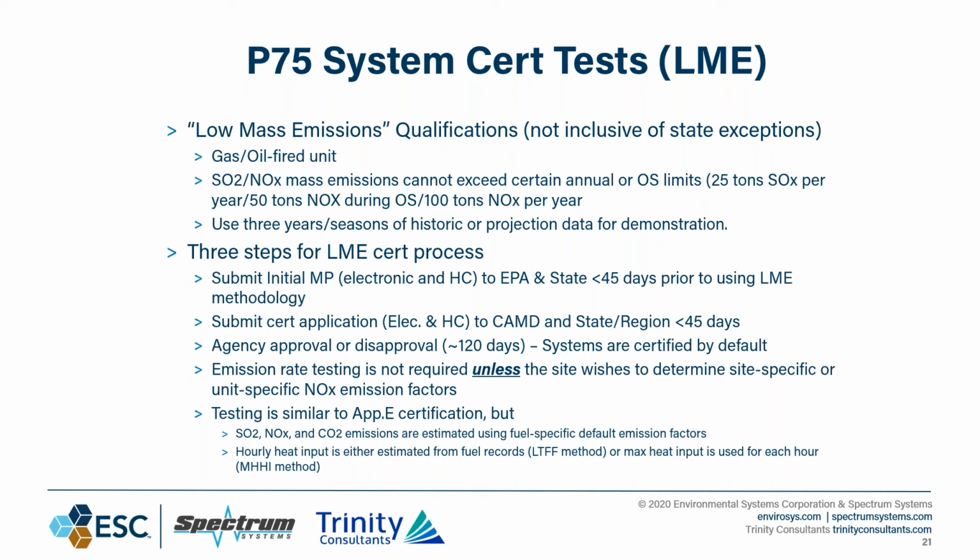Now, emission rate testing is not required on this unless the site wishes to determine a site-specific or unit-specific NOx emission factor. There are pluses and minuses to that I won't get into. But the takeaway here is that your testing is very similar for LME to Appendix E certification, with the exception that your mass emissions are estimated using fuel-specific default emission factors.